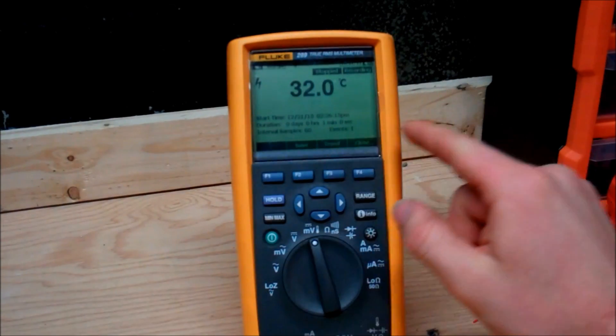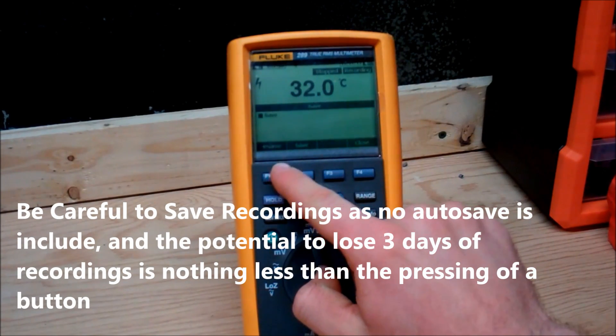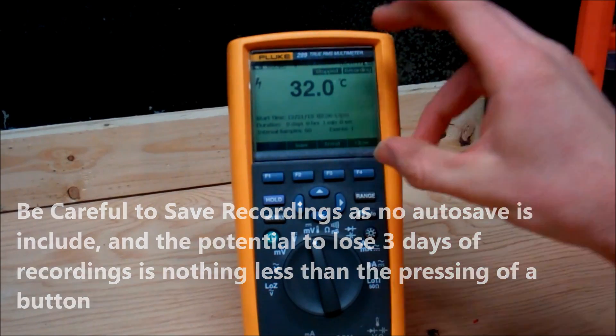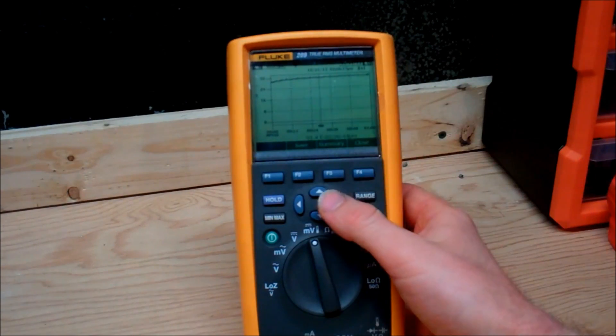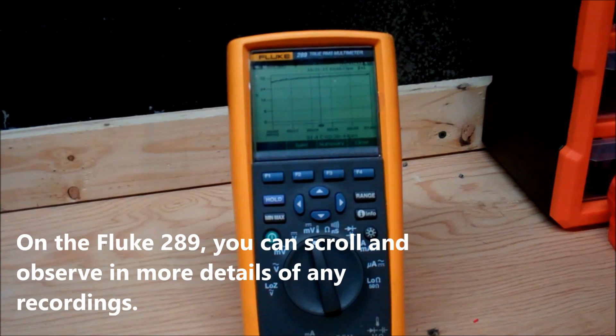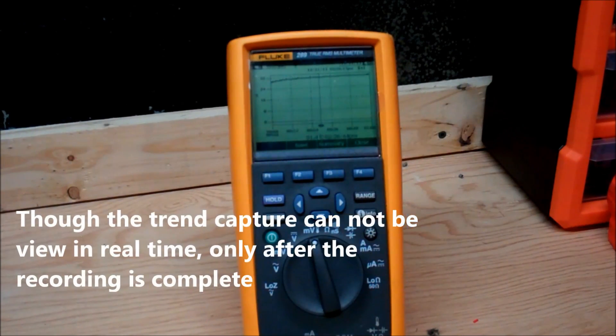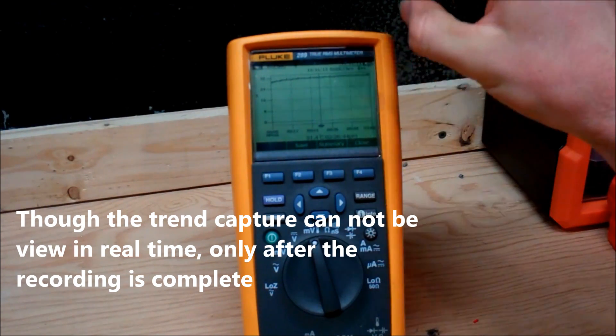Now we just finished our recording here and they give you three options: save, trend, and close. First off, save it, you can rename it or whatever you want but it's relevant to time too. It also puts a time stamp on it so it's really nice and convenient that way. Then you can click the trend pattern to see what occurred when you're taking that measurement. It's really nice because now you can really make relative comparisons to time. If you're taking a reading over a voltage bus or something like that and you see a transient spike, you can track down what motor is giving you that terrible transient spike in your system. So as you can tell there's a lot of really amazing ways to troubleshoot new circuits with this.